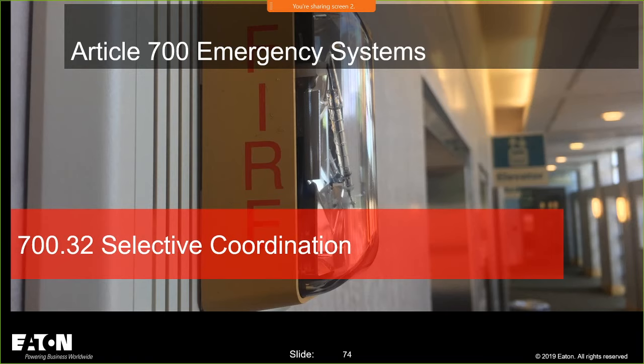A majority of those on the phone would say that the breaker downstream of that F-150, the breaker, not the truck, was selectively coordinated, without knowing that they've got to compare available short circuit current. And if you don't know what the selective coordination tables are, go back and watch. I've got 2 videos, one for fuses and one for breakers on my channel. And I have the session from 2 Tuesdays ago that basically talks about selective coordination. You should watch that video as well.